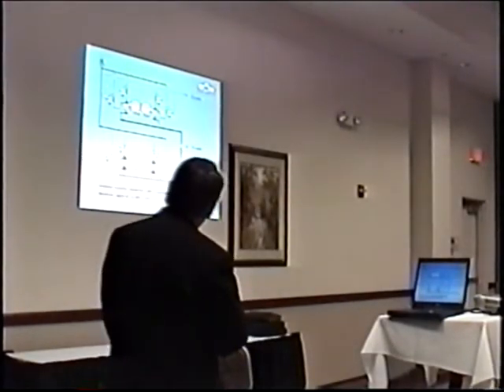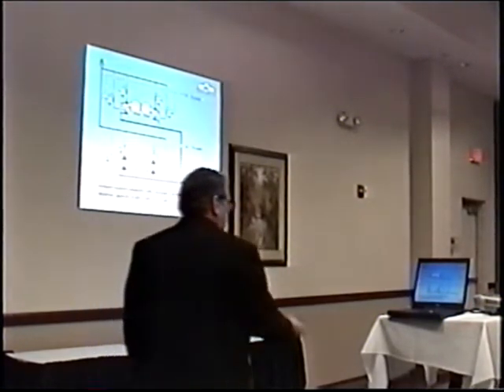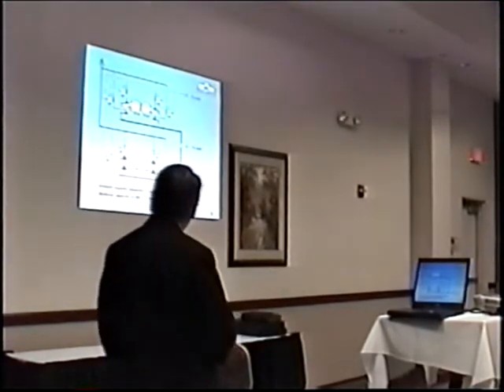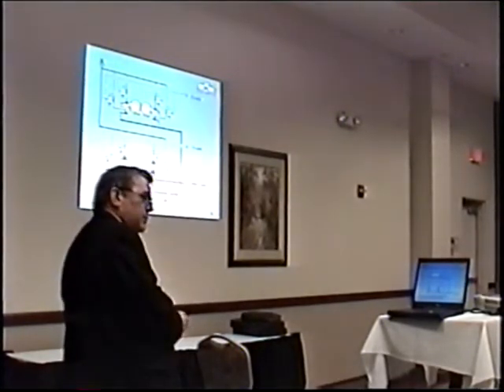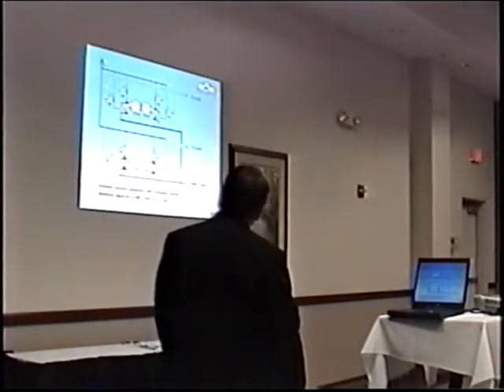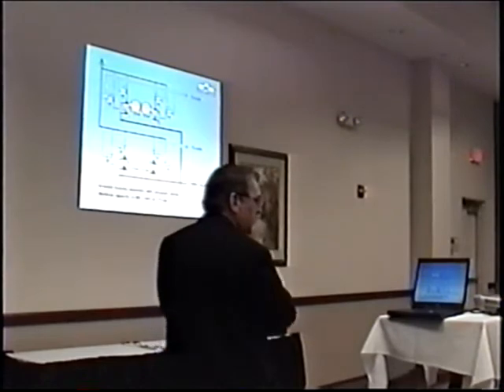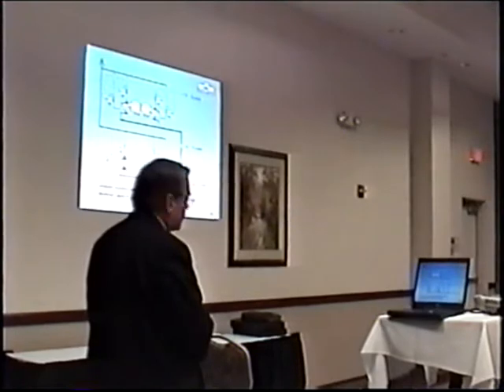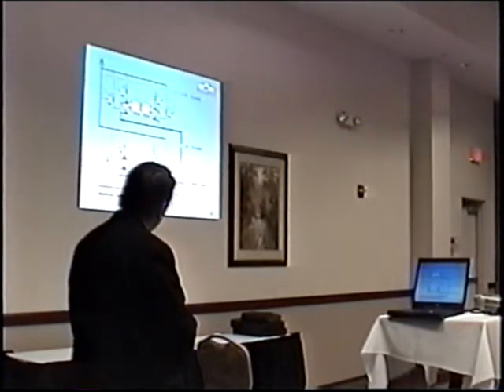What's good about this system is that you can match positive displacement pumps, which have a fixed output, to a variable demand system. If 1 nozzle opens, 2 nozzles open, 3, 4, 5, 6, 8 nozzles open, there's a variable demand. So how do you match a positive displacement fixed output pump system to that? Well, one thing is to use several small pumps, each with its own unloader, working in a nice comfortable range. Say these unloaders are good for 2 to 20 gallons per minute. That's perfect for these sizes of pumps.